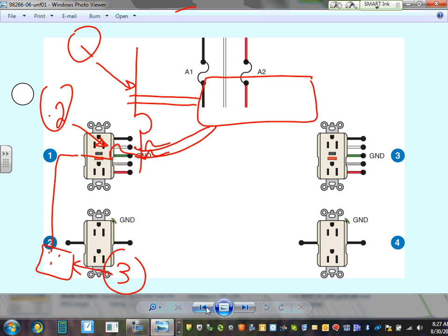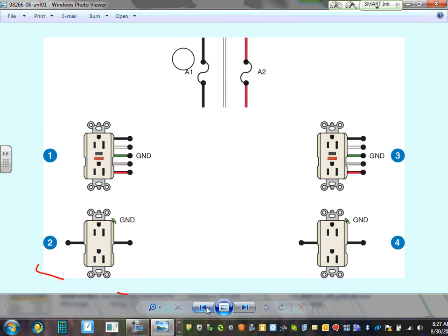Any questions, guys, before I finish wiring this and let you go, lecture-wise, for today? Any comments? So we talked about devices that protect you when you distribute your power system: GFCI shock protection in any wet location, and AFCI arc protection against fires in a building, everywhere in the house that doesn't have a GFCI, receptacles and lights. Then we talked about tamper resistance in every receptacle, 15 and 20 amp, 120 volt. And then we talked about weather resistant. Any receptacle in a damp or wet location must be, again, to maintain the integrity of these devices. And the last thing I believe we talked about, guys, is surge protection. That will be right at the panel or just a receptacle, or it could be a circuit breaker, or it could be a power strip like you've seen.